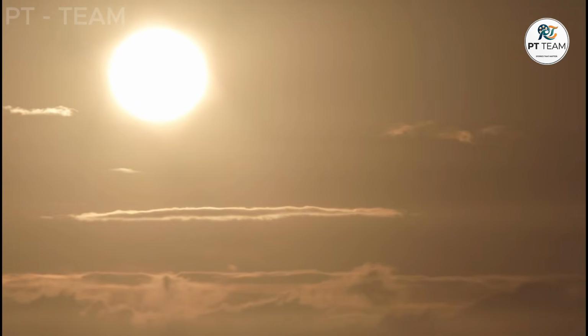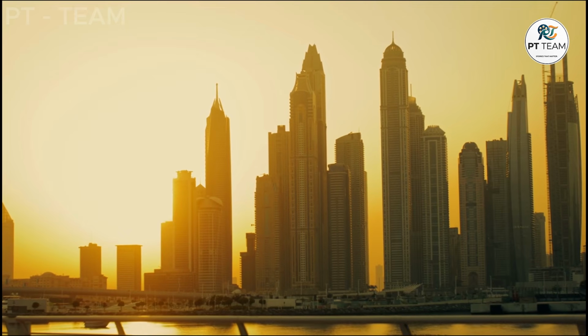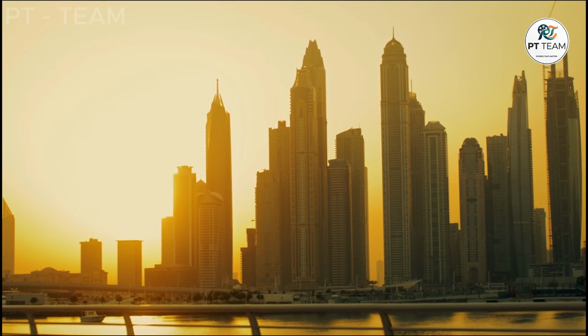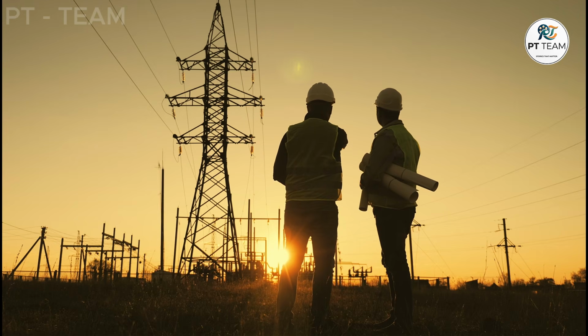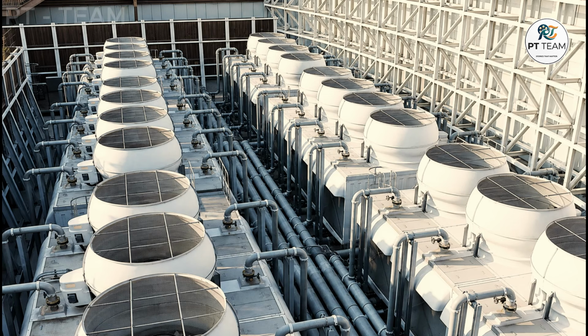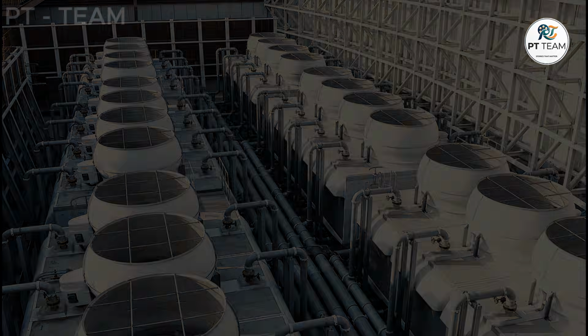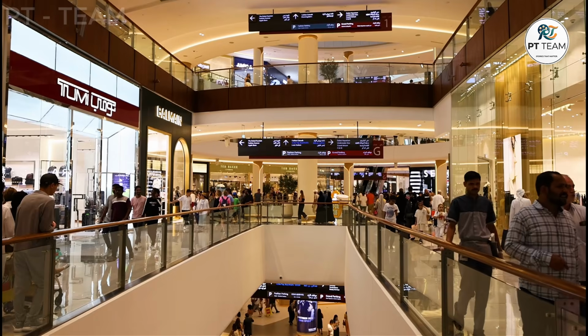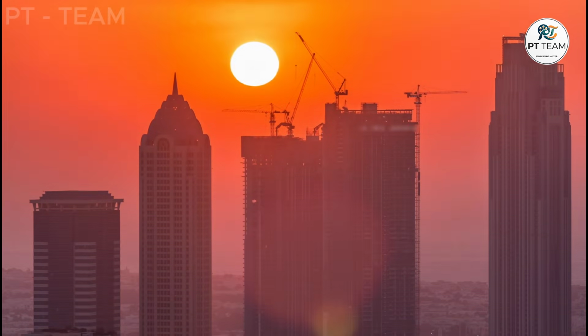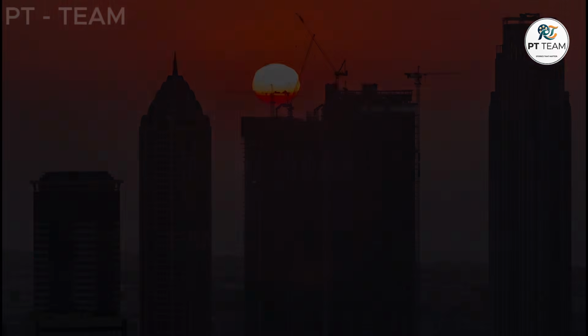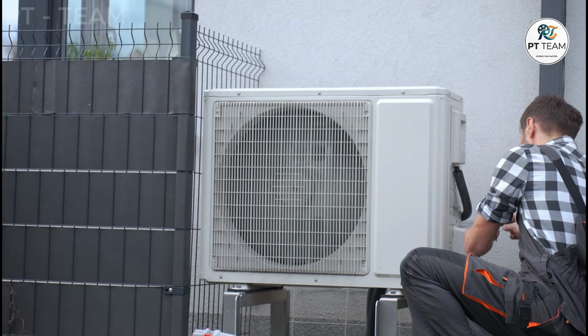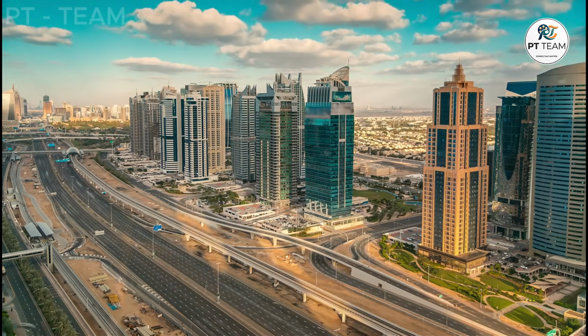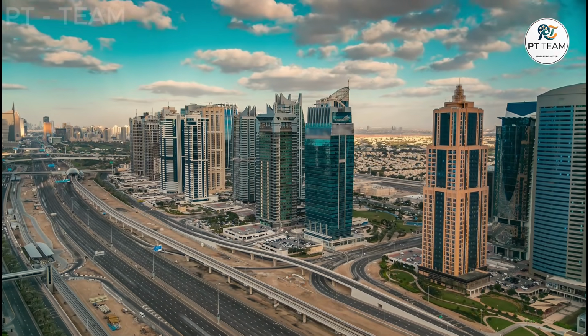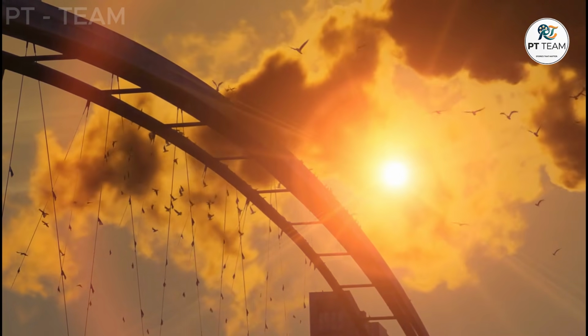Between 12 p.m. and 6 p.m., the city experiences its most intense peak in solar heat absorption and daily electricity demand. This is exactly when enormous district cooling systems must satisfy the thermal load of hundreds of thousands of people simultaneously. If that infrastructure loses its operating margin during a severe stress event, the occupant cannot solve the problem by repairing a small outdoor unit. The true source of the issue could be kilometers away, and the atmospheric variable making this heat rejection difficult is not always the dry temperature you look at on a weather application.